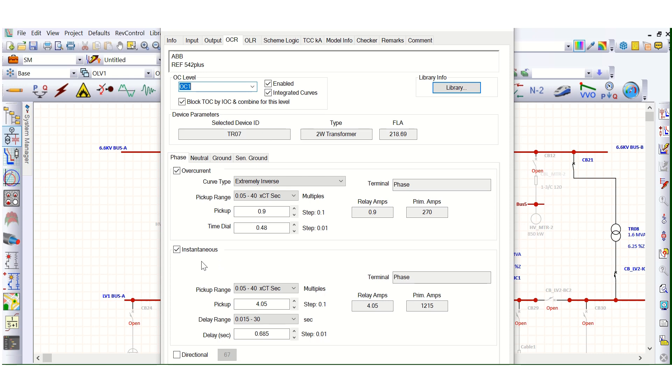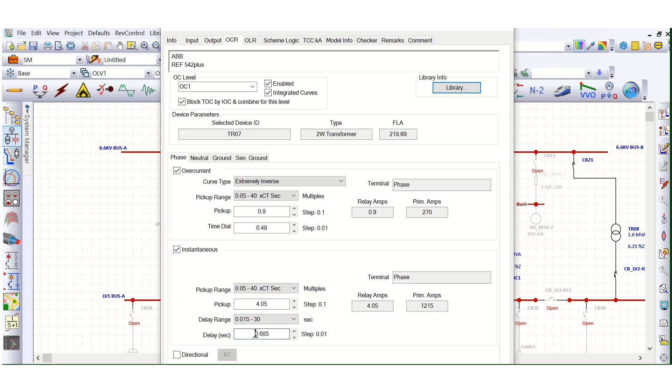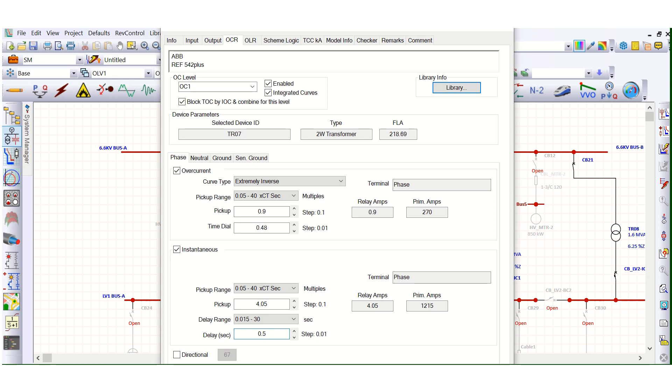But we can use this instantaneous as a short time delay. Suppose, here I have used short time delay. Let's say 500 millisecond, that means 0.5 second. This is in second. But for 51, this is time dial. This is not in second. This is time dial setting. 0.48, this is time dial.